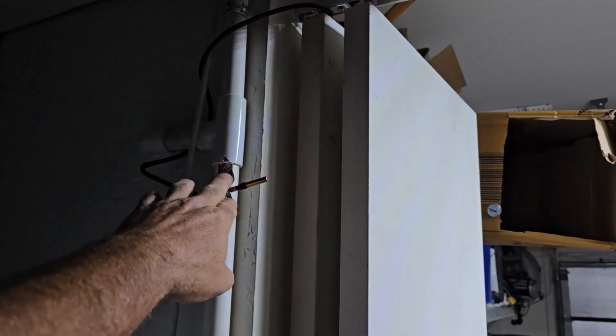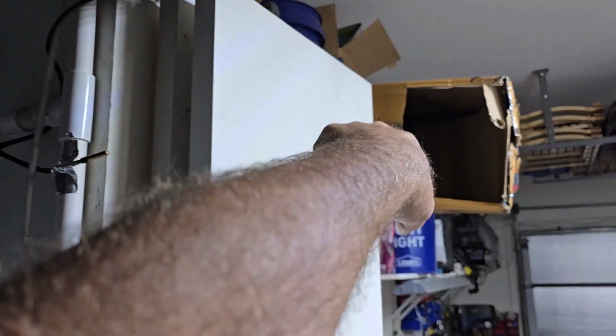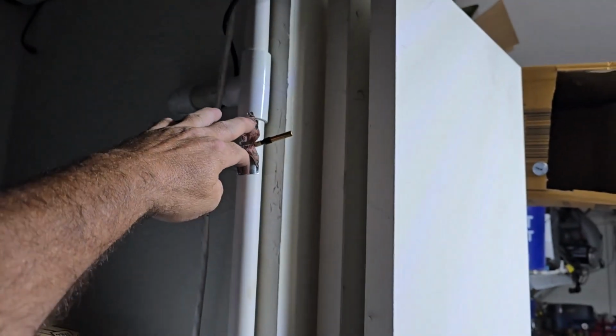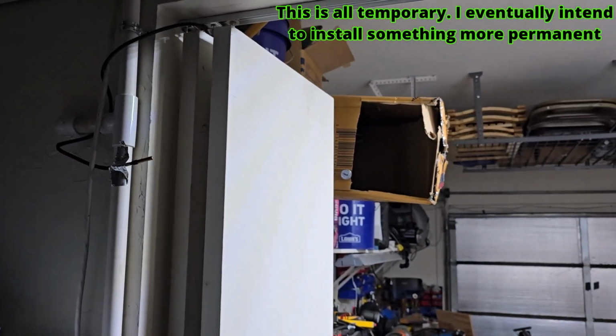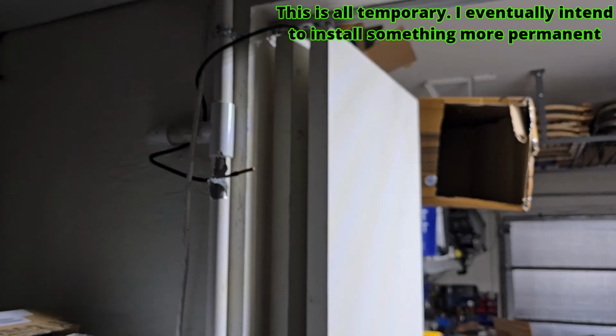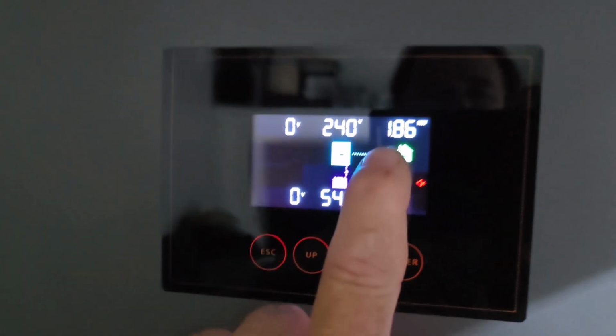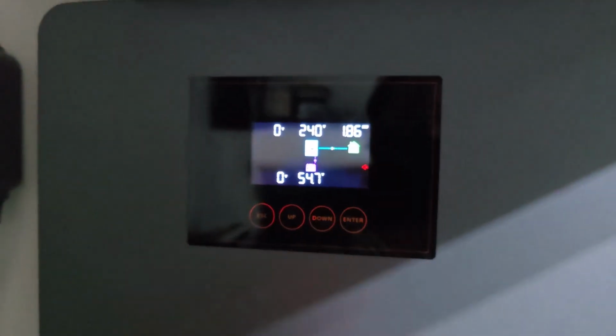So I put the return air sensor for that fan coil one kind of right here. It's not in the air path, but it's in the area that starts dropping a temperature once cool air is blowing in here. And that way that one will just back off a little bit, shooting in this room, and that does help this start dropping in the kilowatts. So it's 1.86 kilowatts to run both heads right now.